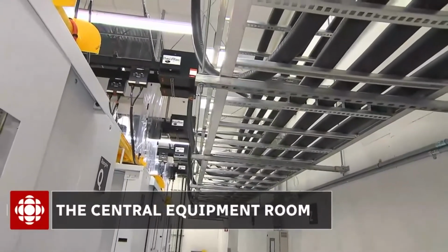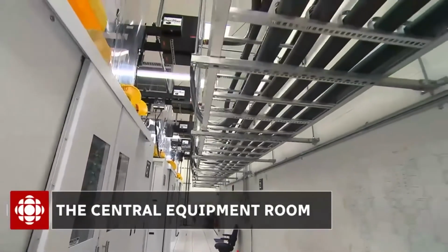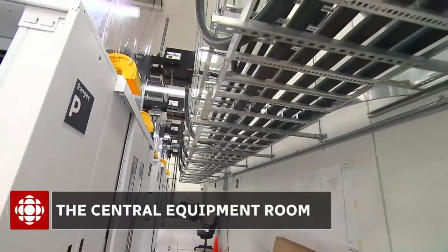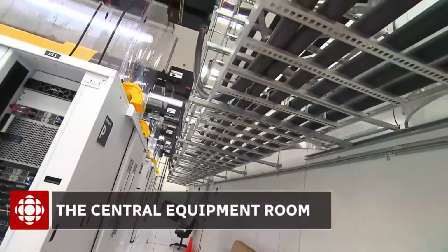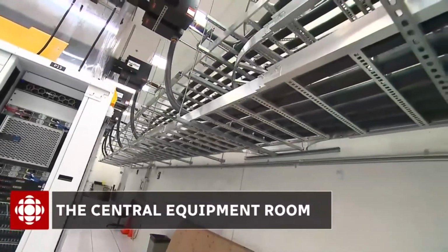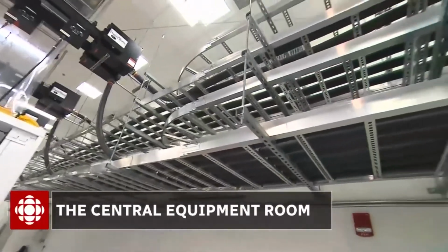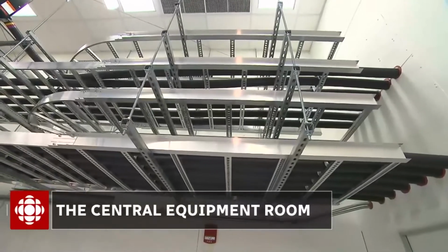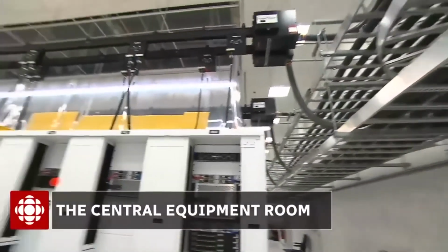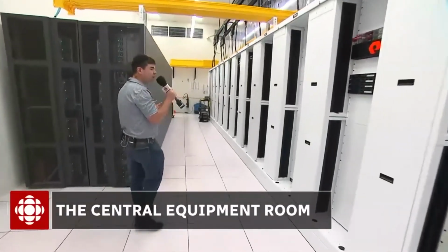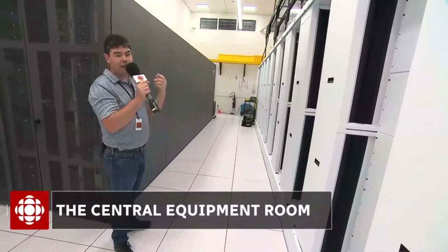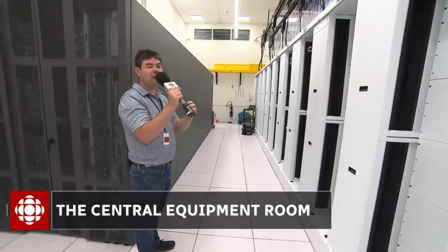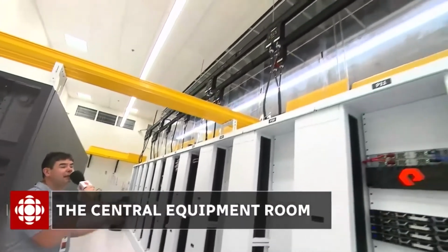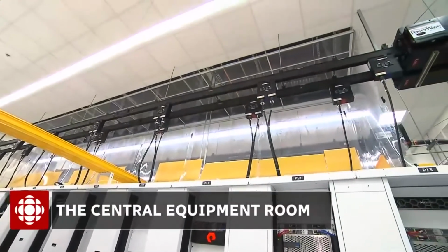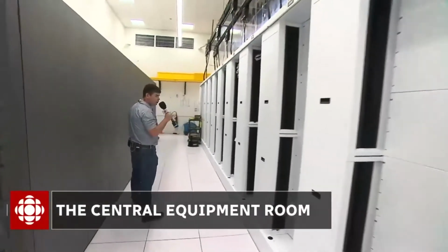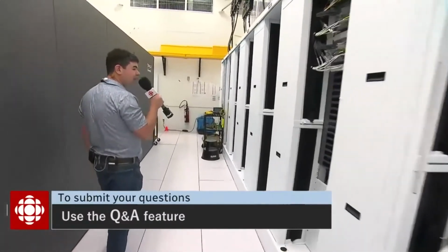So in both rooms combined, we have 12 rows of 13 racks each, for 156 equipment racks. The rack layout uses hot aisle, cold aisle air confinement. Right now we are sitting in the cold aisle, so we can see the grill from above. We get the supply of fresh air from the upper side of the wall. The cold air goes into the room, gets sucked through the equipment, and is expelled on the back where we have hot air containment. It goes back to the ceiling and then to the CRA unit again, circling back like this. During winter, we recover the heat generated by the equipment to heat the building.